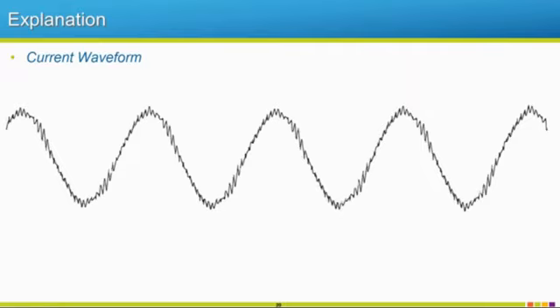So as you increase your carrier frequency, what do you think's going to happen to this sawtooth pattern? Probably going to get a lot smaller and smoother, right? So our current waveform going to our motor will be better. As long as we don't have a lot of voltage transients and long lead length issues, you would be fine with running a higher carrier frequency up to a certain extent. You got to remember if you're switching these IGBTs a lot more often, what happens? Excess heat's going to happen. So these IGBTs are going to heat up quicker. So you may have to deal with the derate, especially if you're loading this up to its full capacity.